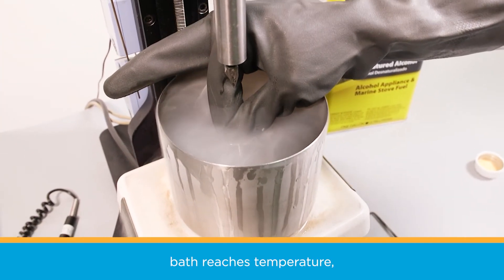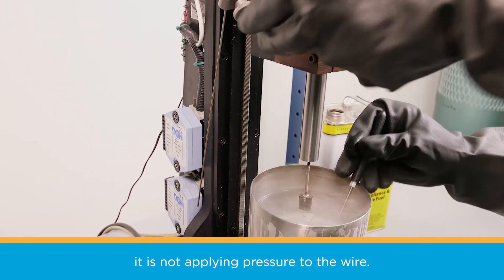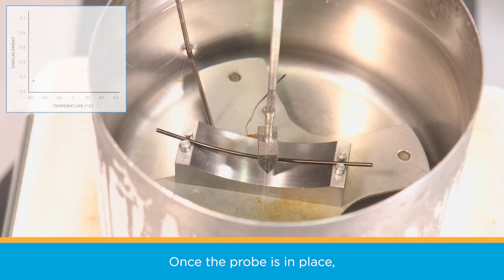When the chilled alcohol bath reaches temperature, use the deforming mandrel and apply enough pressure to deform the nitinol. Position the LVDT probe so that it is touching the wire. Test your counterbalance to be sure it is not applying pressure to the wire — you want neutral buoyancy.